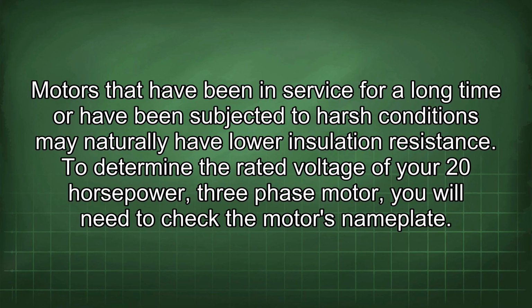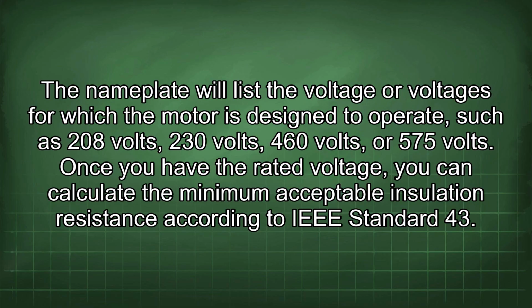To determine the rated voltage of your 20 horsepower, three-phase motor, you will need to check the motor's nameplate. The nameplate will list the voltage or voltages for which the motor is designed to operate, such as 208 volts, 230 volts, 460 volts, or 575 volts. Once you have the rated voltage, you can calculate the minimum acceptable insulation resistance according to IEEE Standard 43.